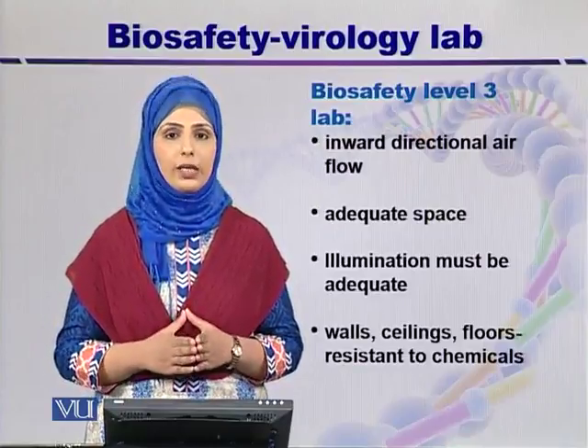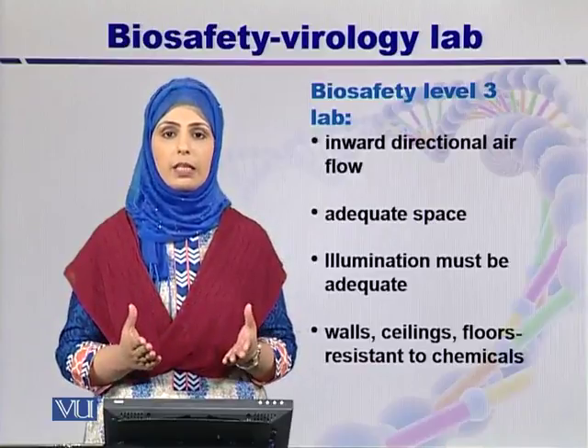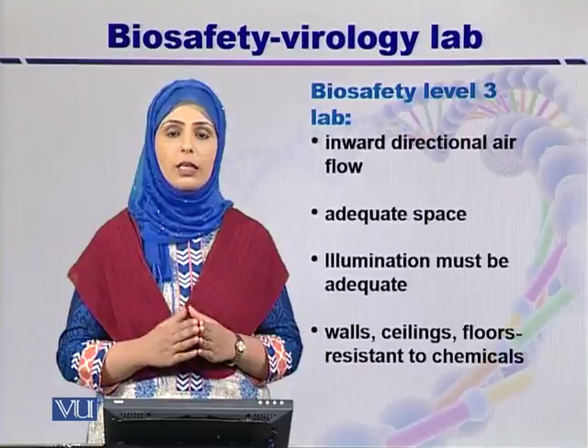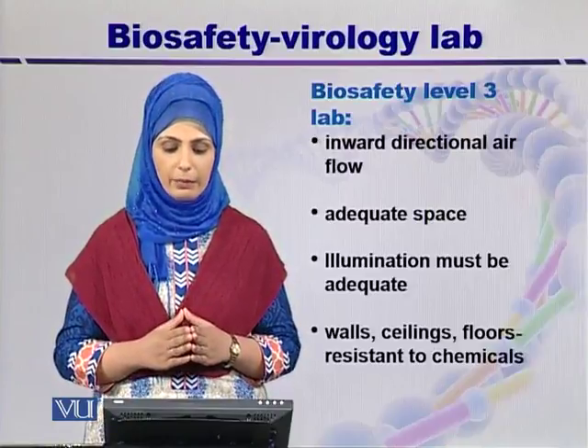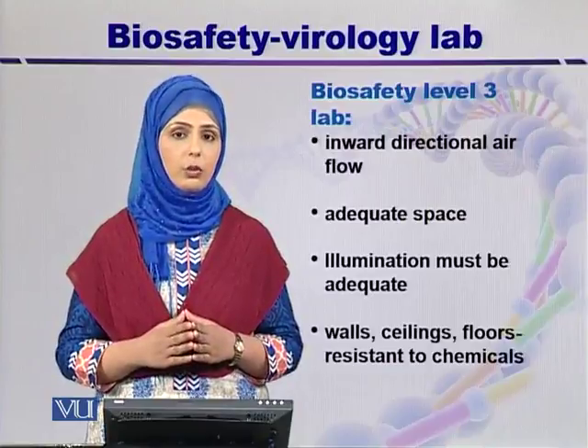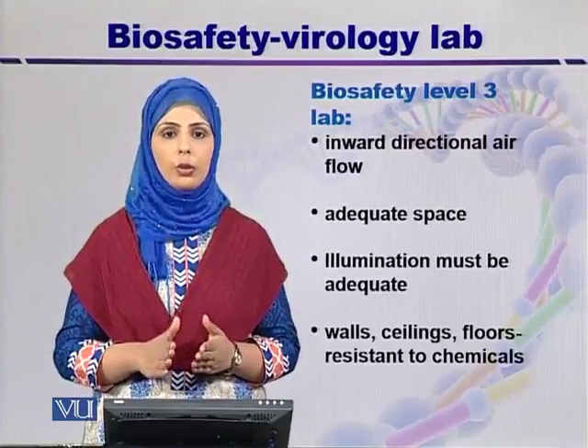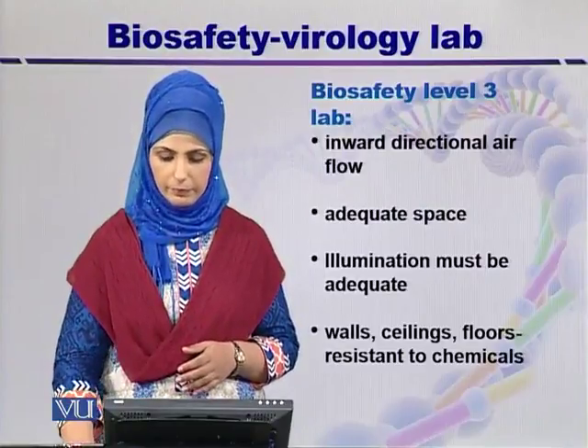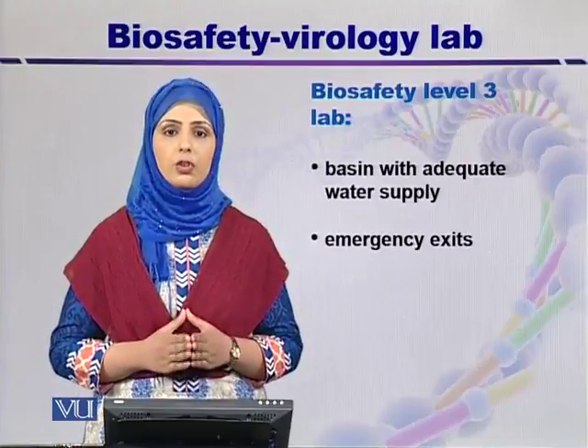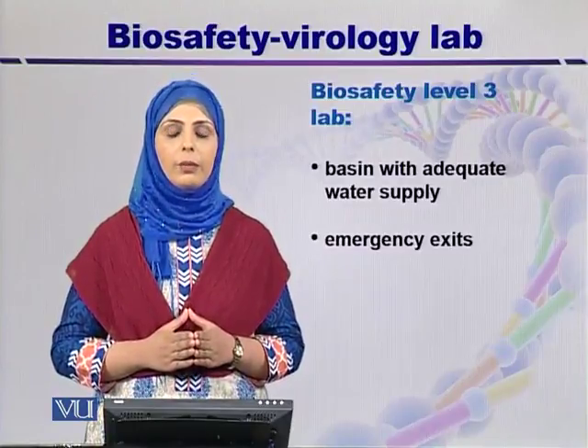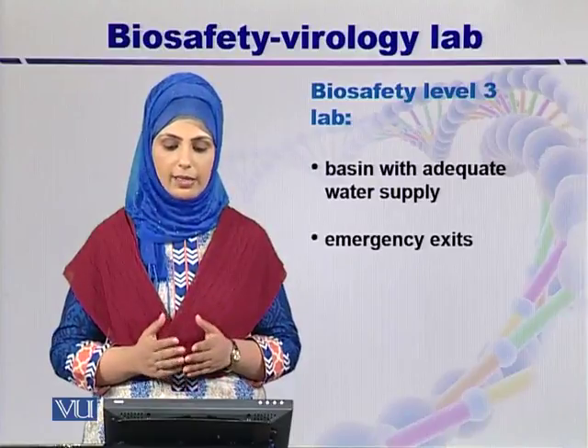There must be adequate space between benches, with techniques performed on separate benches, dedicated space for microscopy, and separate rooms for washing and sterilization. Adequate water, electricity, and gas supply are required. Walls, ceilings, floors, and bench tops must be resistant to chemicals and alkalis. Basins should be near the entry and exit doors with adequate water supply and hand-washing soap for decontamination.